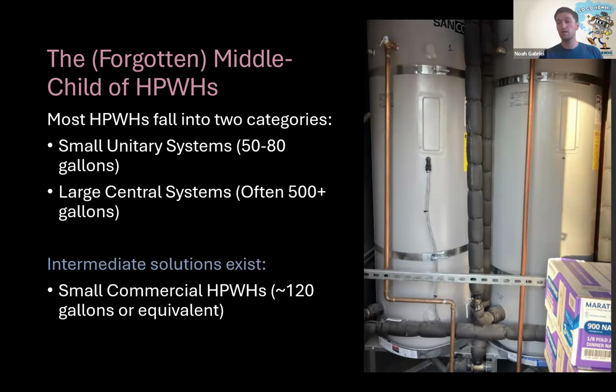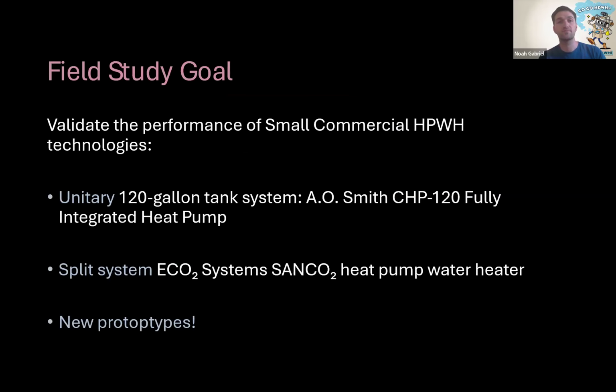Luckily, some great alternate solutions exist in the form of small commercial heat pump water heaters, like the CHP 120 from A.O. Smith, or split systems like the ones produced by Sanco. You can see an example of the tanks in this picture. Those are usually around 100 to 200 gallons of total capacity depending on your setup, and often around 4 or more tons of heating capacity. That's about 40,000 to 80,000 BTUs, depending on temperature inside and outside.